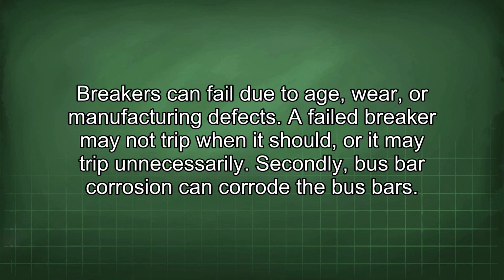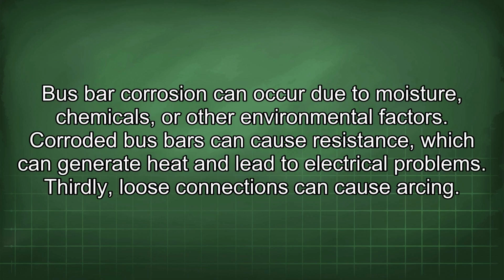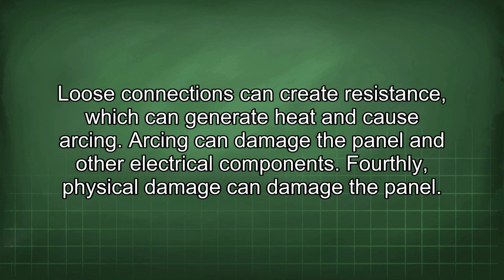Secondly, bus bar corrosion can corrode the bus bars. Bus bar corrosion can occur due to moisture, chemicals, or other environmental factors. Corroded bus bars can cause resistance, which can generate heat and lead to electrical problems. Thirdly, loose connections can cause arcing. Loose connections can create resistance, which can generate heat and cause arcing. Arcing can damage the panel and other electrical components.